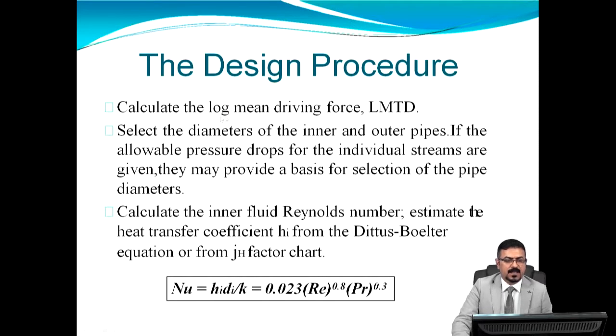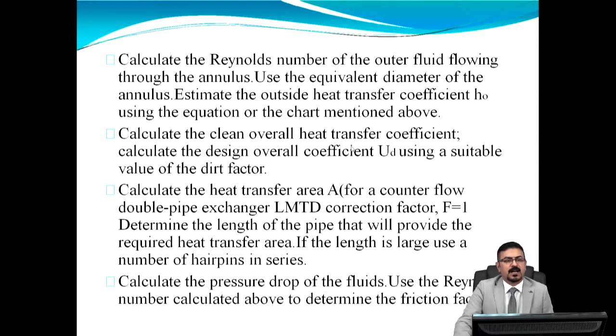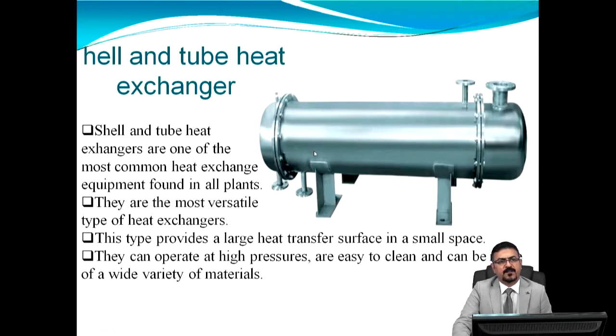The design procedure for a double pipe heat exchanger involves the following steps: calculate the log mean temperature driving force; select the diameters of the inner and outer pipes — if allowable pressure drops for individual streams are given, they may guide selection of pipe diameters; calculate the Reynolds number of the outer fluid flowing through the annulus; calculate the clean overall heat transfer coefficient; calculate the heat transfer area; and calculate the pressure drop of the fluids.